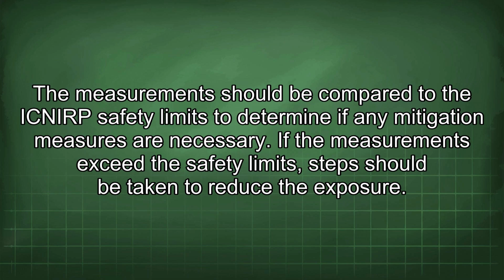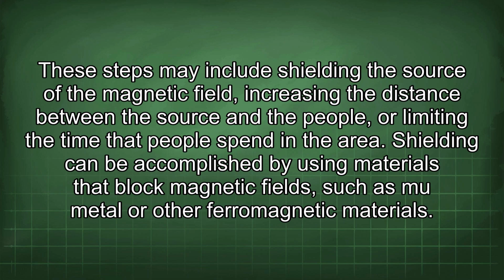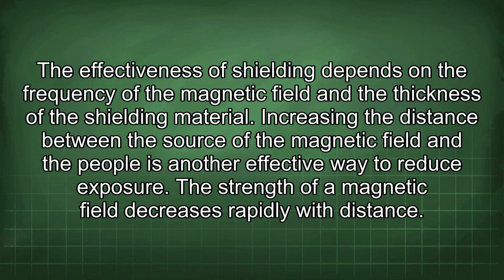If the measurements exceed the safety limits, steps should be taken to reduce the exposure. These steps may include shielding the source of the magnetic field, increasing the distance between the source and the people, or limiting the time that people spend in the area. Shielding can be accomplished by using materials that block magnetic fields, such as mu metal or other ferromagnetic materials. The effectiveness of shielding depends on the frequency of the magnetic field and the thickness of the shielding material.